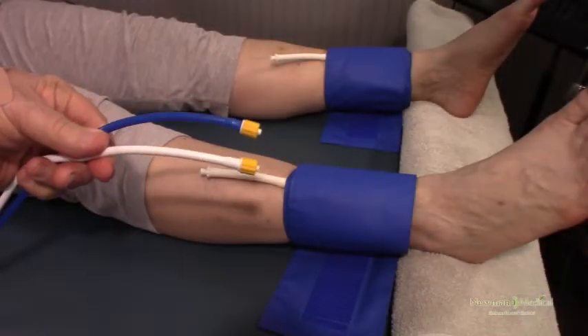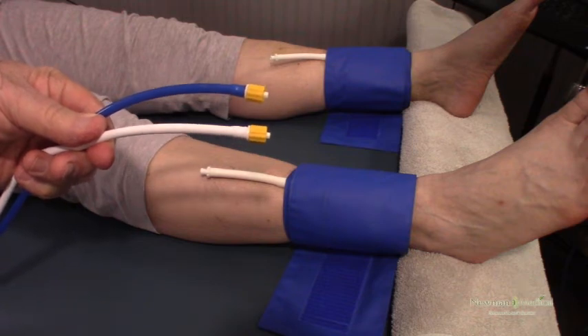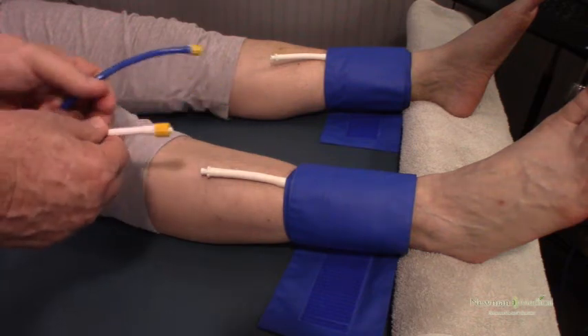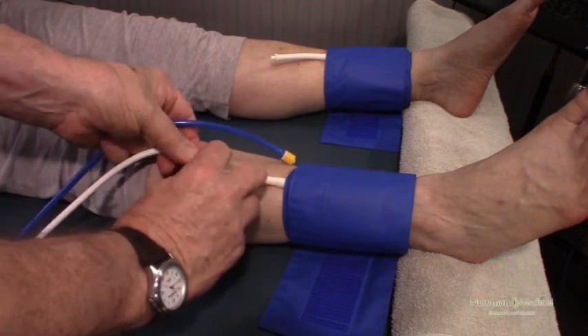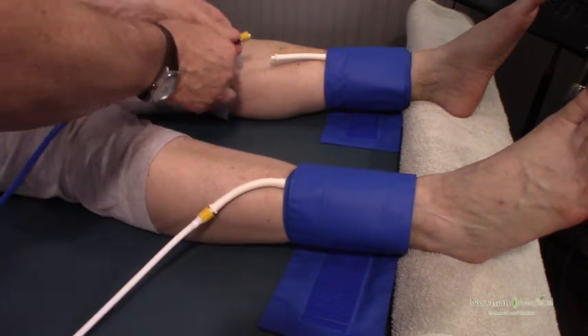Attach the hoses from the cufflink control unit to cuffs. The yellow connectors go to the ankles. White hoses go to the patient's right side, blue to the left.